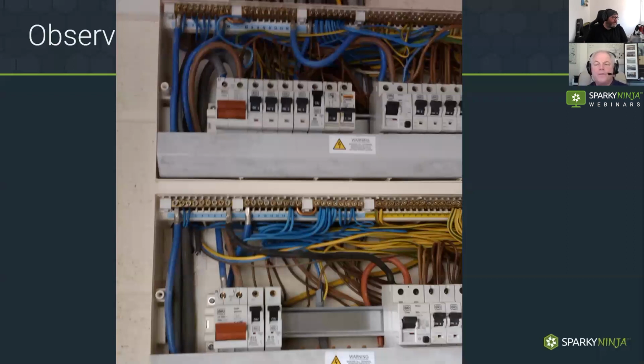All right, what do we see? One means of total isolation, doubled up on income. We'll look at the neutral. Okay, so let's see what we can see here. Okay, and I took this picture because I just had to stare at it for 5 minutes. That's not right. Supply comes into the top main switch here. We then feed the bottom board from this supply side of this isolator, but the neutral feeding this board is actually from the neutral bar. So if I switch this top breaker off, but keep these on, what happens to this installation down here?